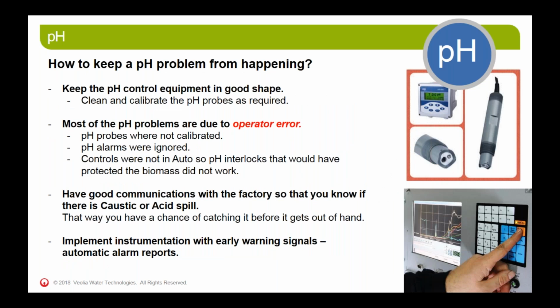Next. So how do you keep this from happening? How can I reduce the possibility of there being a pH problem? I can't emphasize enough how important it is to keep the pH control equipment in good shape. This means that the pH probes should be checked. The inline pH probe should be checked daily and cleaned and calibrated as required. The pH control equipment, whether they're individual loop controllers or a control package or part of a PLC.